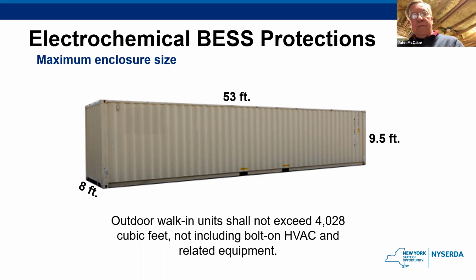Well, something has to come down from the Office of Fire Prevention Control. And we have to get trained because somebody's going to get hurt. You've got to be trained in this. And I only did this because I've been in the power field. I worked for Orange and Rockland in the powerhouse as a 35-year electrician. We had huge lead acid storage batteries. Each room had 120 batteries in there. Each battery is half the size of a refrigerator. And we had to worry about hydrogen gas because that's very explosive. On a hot day, it has to be air conditioned and ventilated.